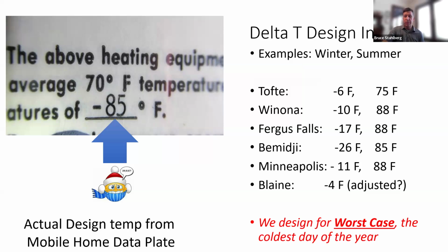We do design for the very worst case scenario. So for example, let's take Bemidji at minus 26 degrees Fahrenheit. This is according to the ACCA, Air Conditioning Contractors of America, Design Manual J. Now, some days in Bemidji, it is 26 below, for sure, but not that often. And so what we end up doing is sizing our systems for the very worst conditions, so that we're able to cover it. But the rest of the time, we're going to be slightly oversized.